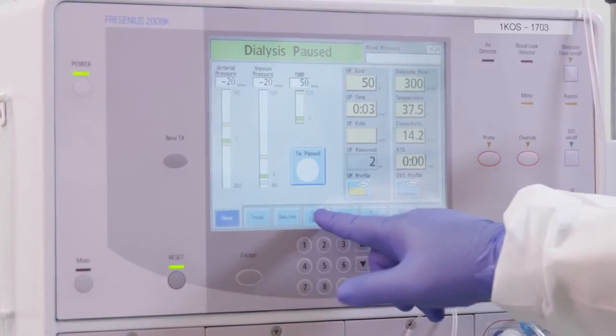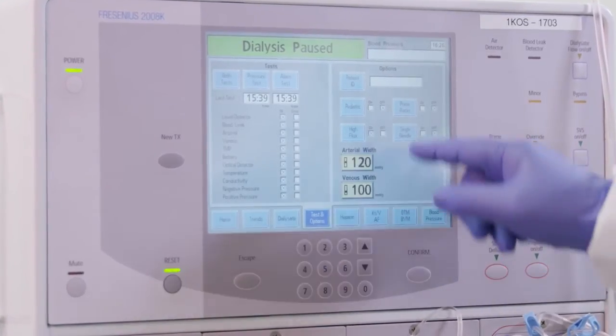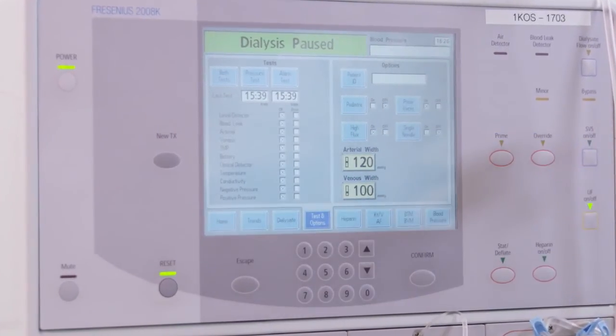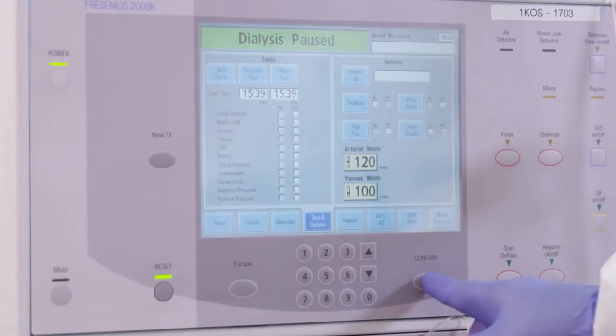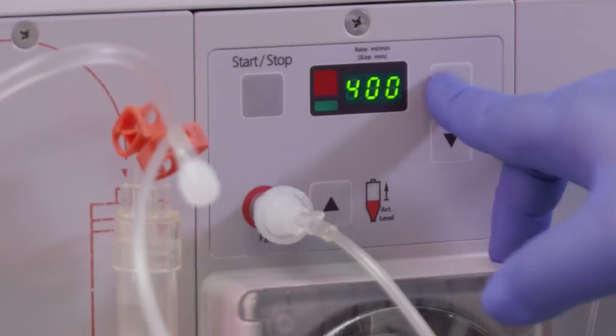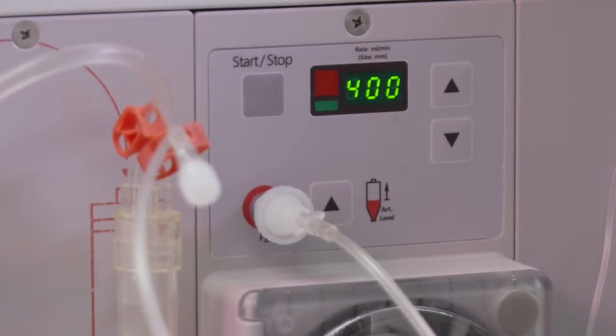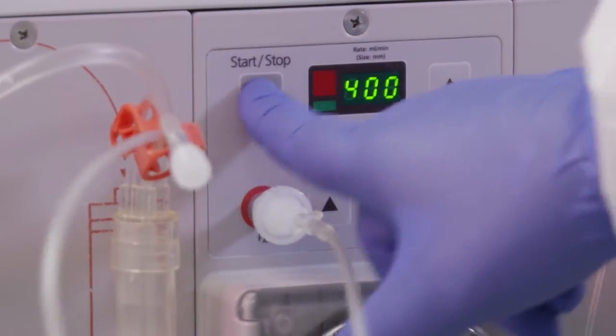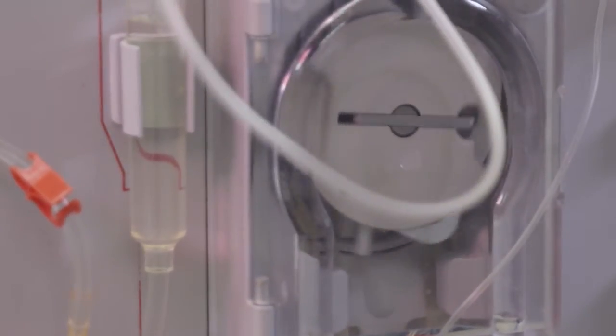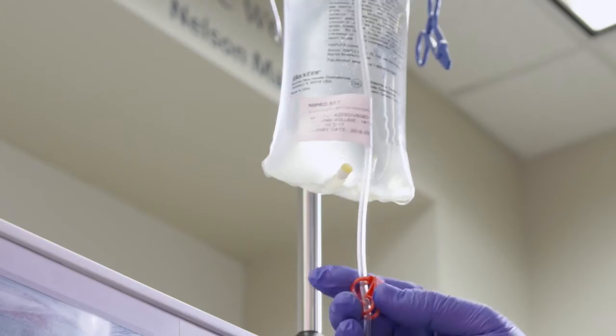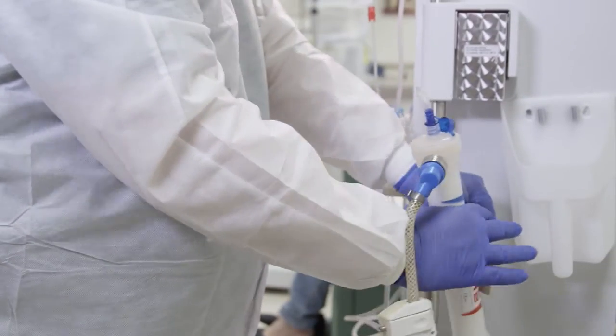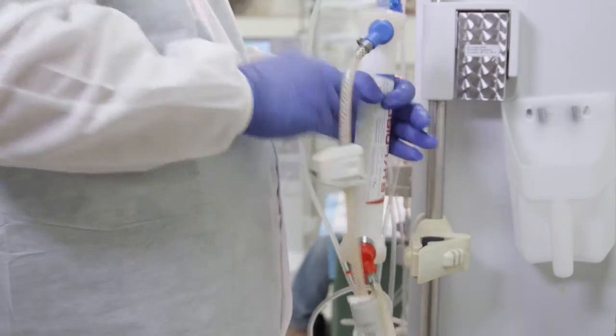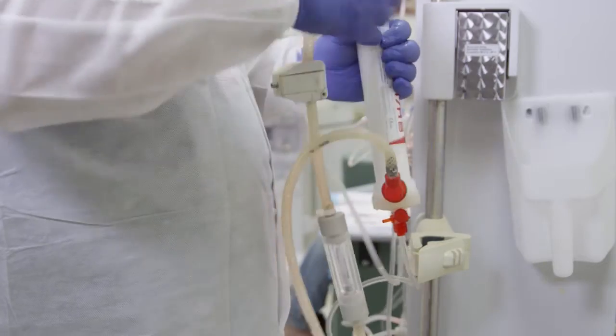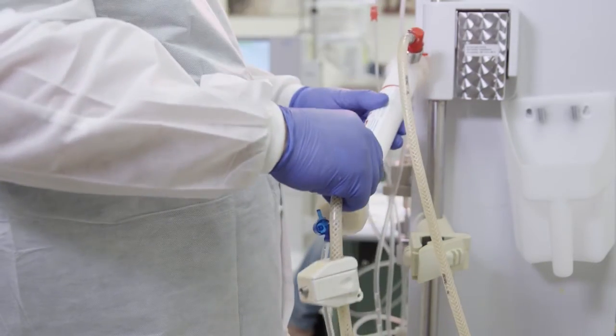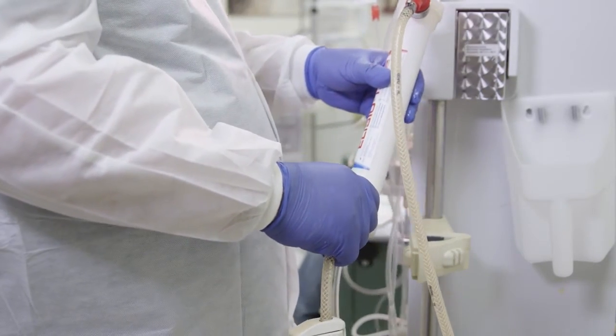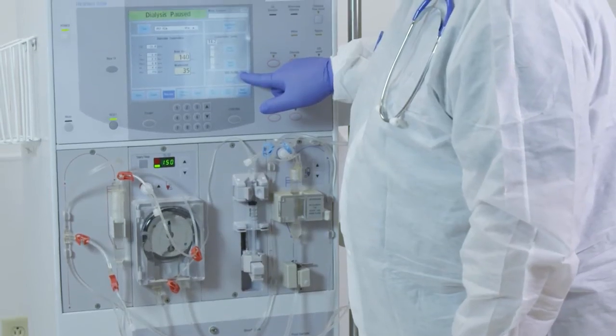On the dialysis machine, press Test and Option, then Prime Recirculation, followed by On and Confirm. Turn on the blood pump to 400 milliliters per minute and recirculate per policy and procedure. Open the clamps on the saline administration set. Approximately halfway through the recirculation procedure, rotate the dialyzer so that the arterial end is up and venous end down. Proceed with treatment initiation per policy and procedure.